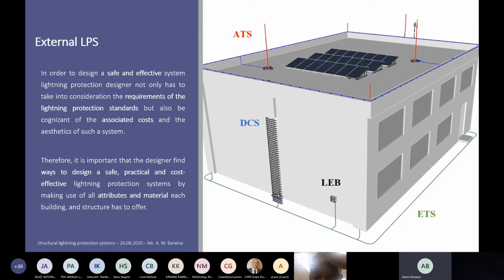So here is a typical example of a school building. I chose a school building because we have been dealing with quite a number of schools in and around countries like Congo, Uganda, and Zambia as well. So here's a typical school. It might have solar, it might not. We see some air termination system marked with red. Those are the catchers, the interceptors. The blue is the down conductor system, conducting it safely down to earth itself. Here we can see that the columns, the natural elements already present in the building, are being used. And then finally, we see an earthing system, or the earth termination system, in green. And we also have the lightning equipotential bonding happening from here on towards the internal side. So here we see the key elements of a lightning protection system, at least the external part.